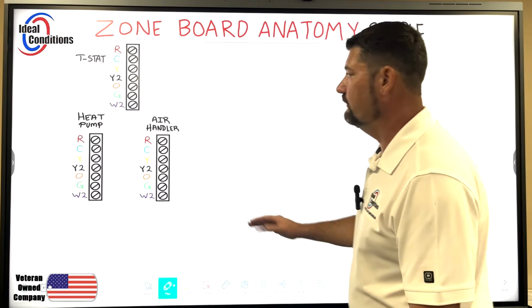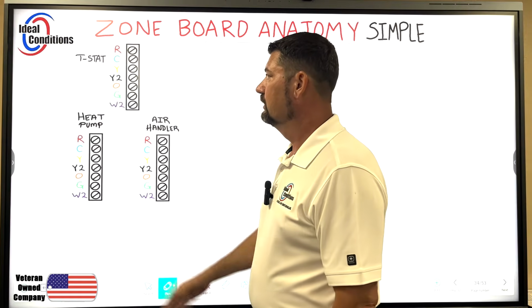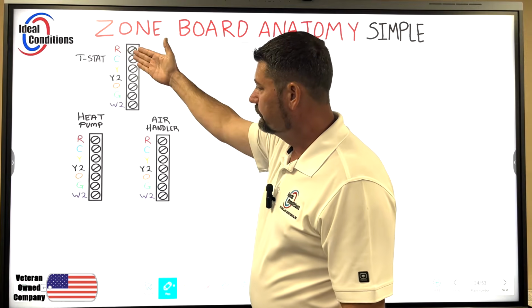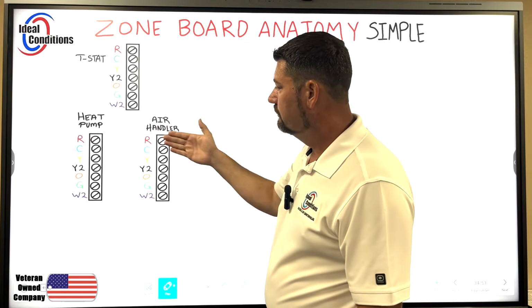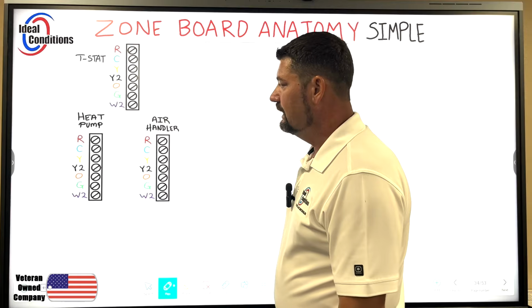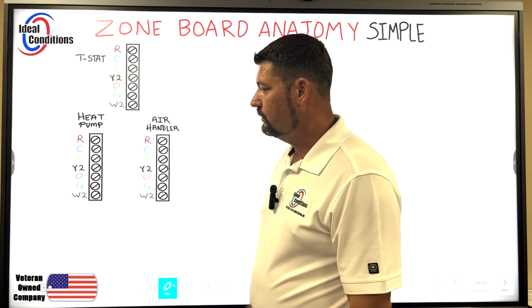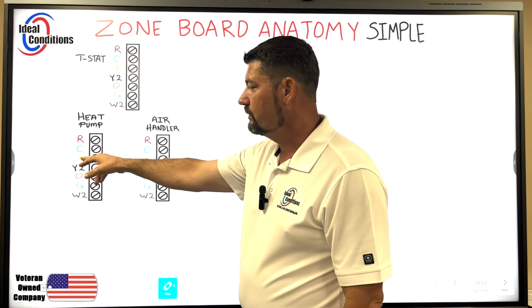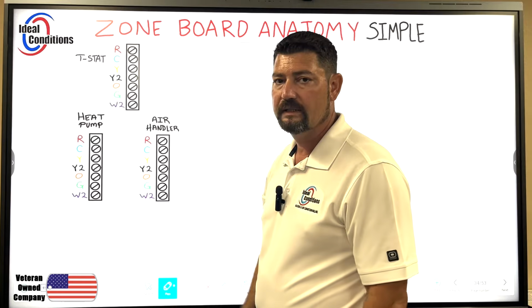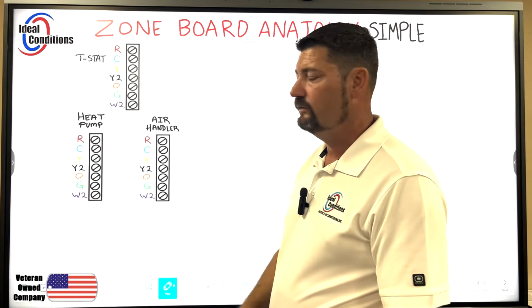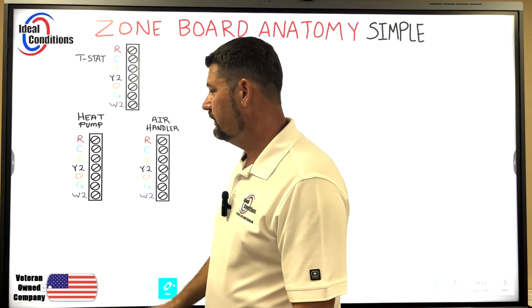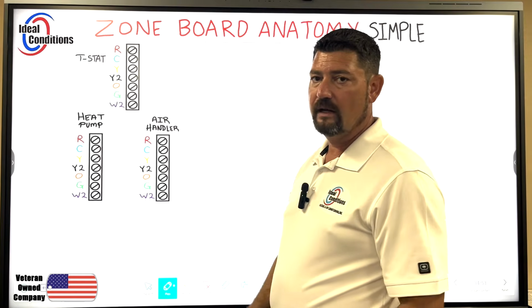Let's look at this - I have three terminal blocks: the thermostat, the heat pump, and the air handler. Now this could just be a straight cool, so you'd only have two terminals, Y and C. You'd just have a contactor to wire up, you won't even have a terminal block for that. We're taking all the fun out of this if we just talk about how to wire a straight cool, so we're getting right to the meat and potatoes - the complexity of it - the heat pump.